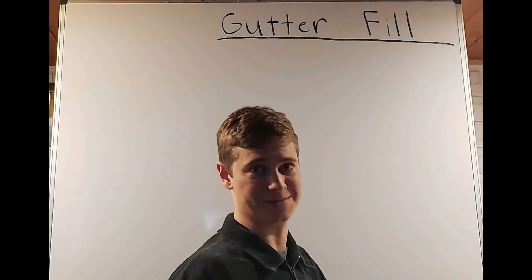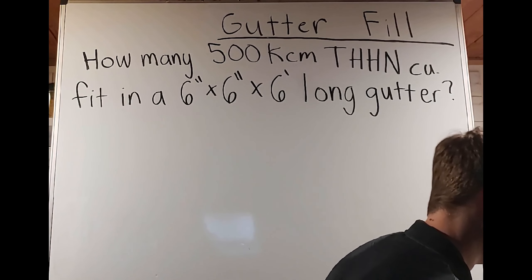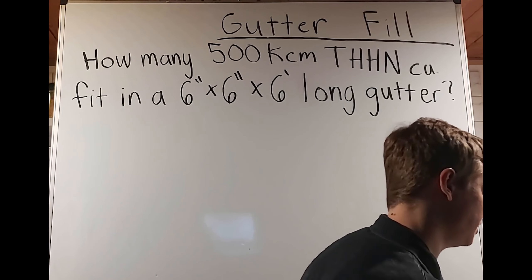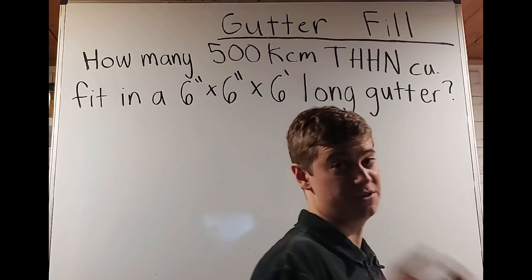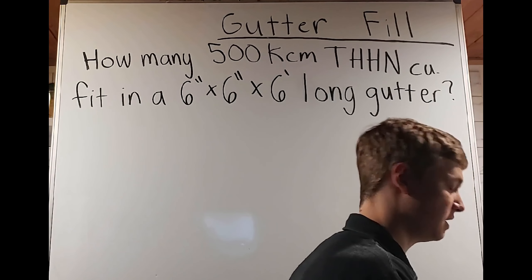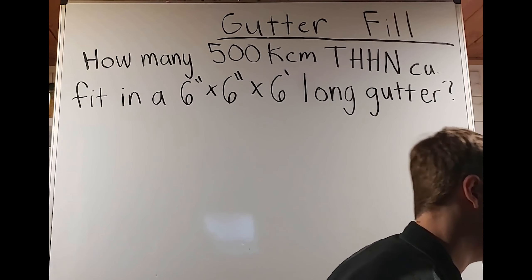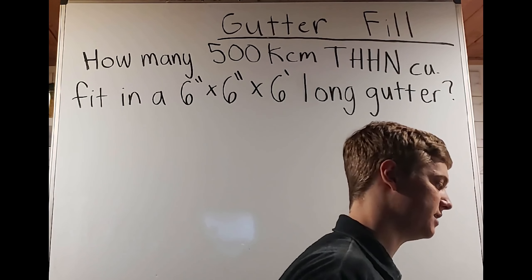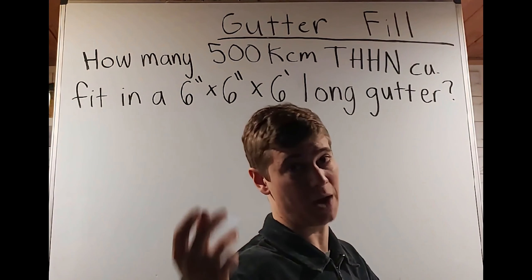This is actually very simple. If we go over to 376.22 of the codebook, where it says A cross-sectional area of wireway, we see the cross-sectional area of all conductors or cables at any cross-section of a wireway shall not exceed 20% of that interior cross-sectional area of the wireway. We also see an adjustment factor for B — if you have more than 30 conductors at any cross-section of the wireway, you're going to want to use adjustment factors in 310.15(C)(1). This only applies to current-carrying conductors, so neutral and hot conductors, not the grounding or bonding conductors.